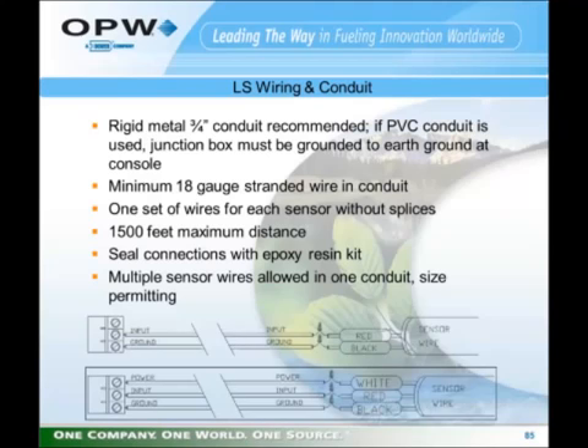If sensors are daisy chained and one sensor goes into alarm, you have no way of determining without exposing all the sensors to see which one is in alarm. So most regulatory bodies will not allow multiple sensors on one circuit to generate one alarm for multiple sensors. So you see on the connectors shown on the diagram, for a 2-wire sensor, we use the bottom 2 terminals of the connector, and for a 3-wire sensor, we use all 3 terminals on the connector.